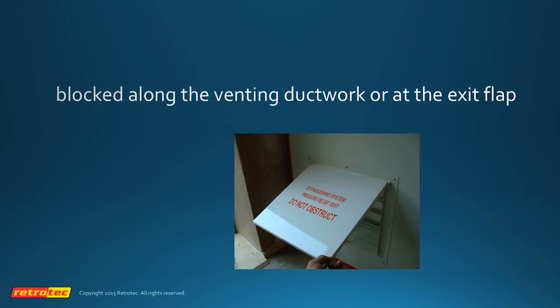So when we measure the enclosure leakage for hold time, we tape the vanes of the vent in position so they don't move. We don't want to seal them up. We just want to stop the vanes from moving. A couple little pieces of tape is all you need to do that. So then when we are going to be performing the venting test, if we have a PRV, we want the PRV to be in the open position. Since we've already done a test of the vent at 125 pascals, we've discovered at what point the vanes are open. Now we have to tape the vanes open in that position in order to measure the entire venting path.